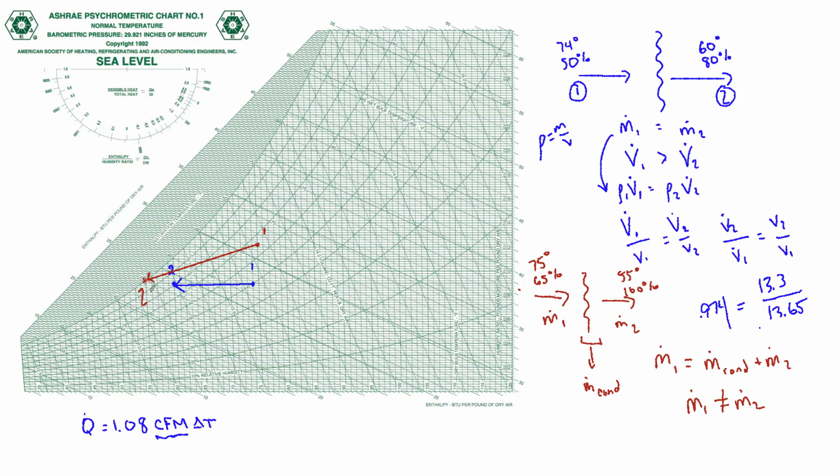Then you're going to take that volume flow rate leaving the air handler that's going somewhere else and follow it there and see what happens next. But if you're really analyzing the air conditioning process, you're analyzing the coil, and you're given the volume flow rate at state 2 leaving the coil, you have to realize that the mass that corresponds to that volume flow rate is not the entire mass that entered the coil because of that condensation that makes up the difference.